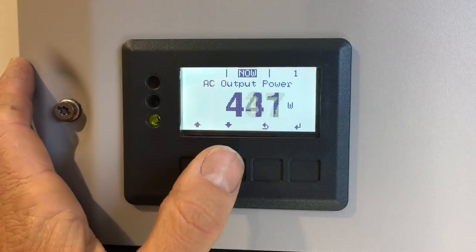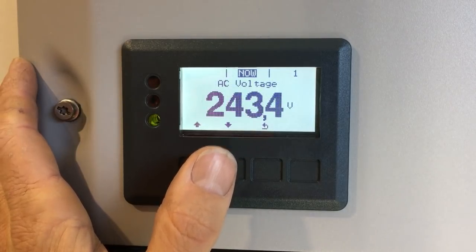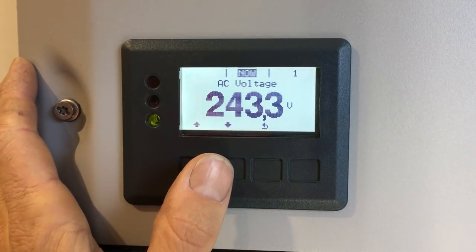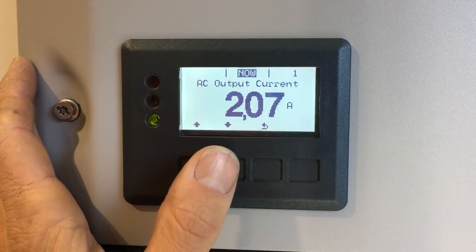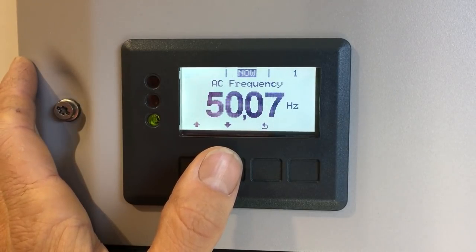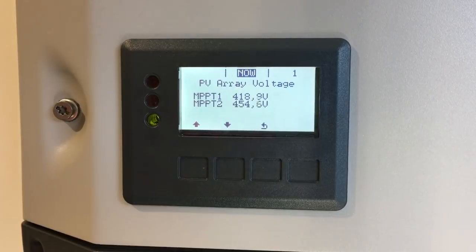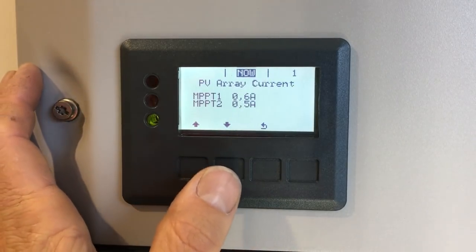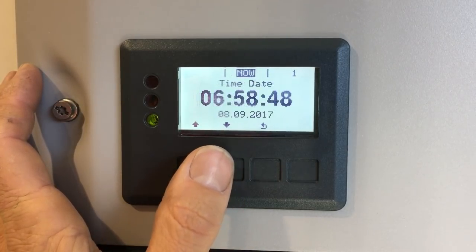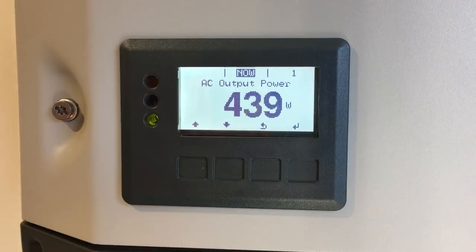Scrolling down through the Now menu shows everything happening with the system right now: AC output power (you don't need to worry about that too much), AC voltage detected from the grid, current going out from the inverter to the grid (2.1 amps at the moment), grid frequency, and PV array voltage. This is a Primo inverter with two maximum power point trackers, so it shows the voltage and current on each tracker input, plus the current time and date.